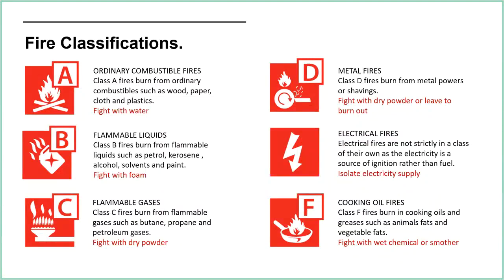So we've got categories A, B, C, D, E, F—oils, metals, gases, liquids—but most of the time we're dealing with category A fires: wood, paper, cloth, plastics, the kind of stuff found in residential and domestic buildings, offices, hospitals. They might have some specialist kit, but mostly it's category A. Same with industrial and commercial—unless you're in a specific area dealing with other flammable materials, chances are there's at least 50% category A in fires. So for me, mist systems and sprinkler systems should be best at tackling category A fires, because that is generally what's required.